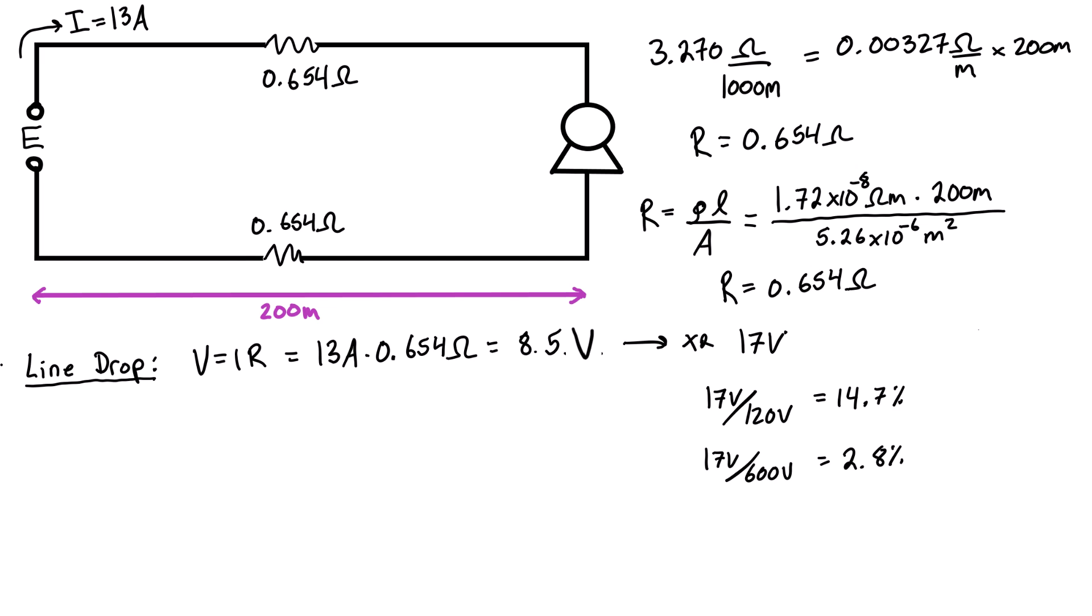That's line drop—17 volts of line drop. Now we want to talk about line loss, and loss is always referring to power. So drop refers to voltage, loss refers to power. We're talking about how much power we're losing due to this resistance in our lines. We're just going to simply use one of our power formulas—in this case it's just going to be I squared R. You might hear about people talking about I squared R losses, and that's exactly what this is—it's the power loss due to the current and the resistance.